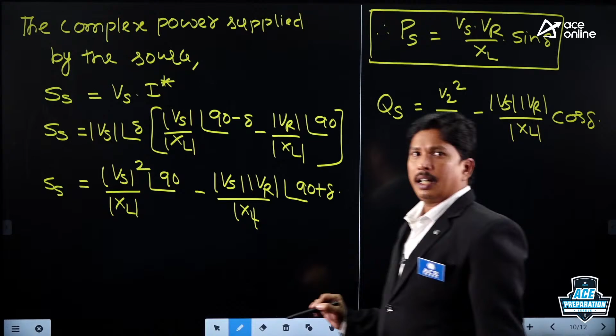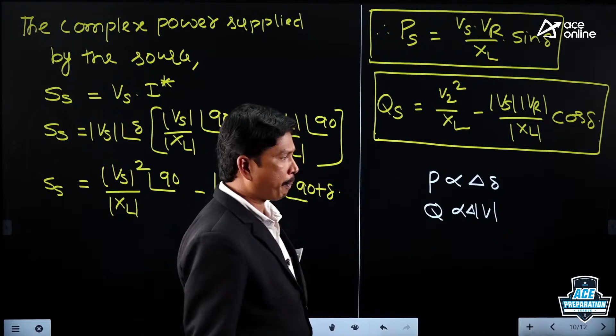From the decoupled equations we have seen, the active power is proportional to change in delta, and the reactive power is proportional to change in voltage magnitude. This means that the active power variation with respect to delta we can consider, but with respect to voltage we can neglect. The reactive power variation with respect to voltage we can consider, and the reactive power variation with respect to delta we can neglect.